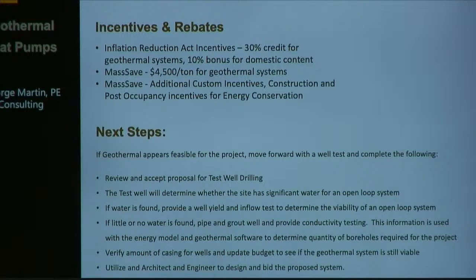The test well determines whether the site has water, and whether you could use an open loop system instead, which is always an option. If we do find water, sometimes we do a capacity test or yield test to see how much water that well can produce, and then we'd do an inflow test, using a hydrant to inject water back into the well to see if it can accept it. Casing and other factors are things we look at to optimize the borehole field, minimizing costs while making sure you have the right capacity.